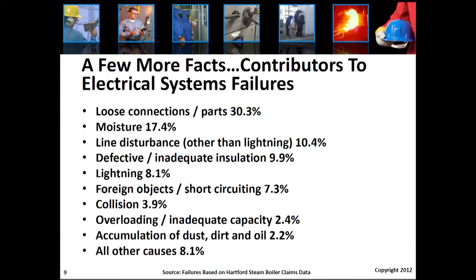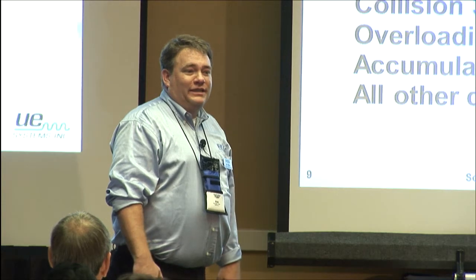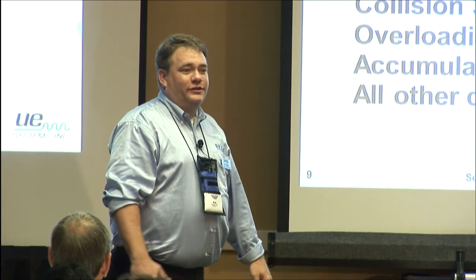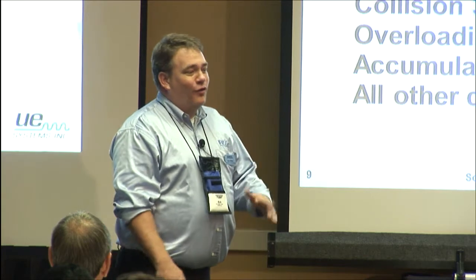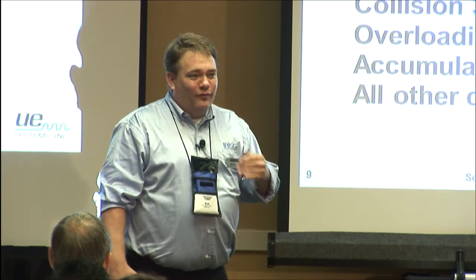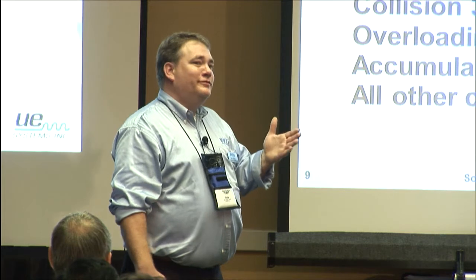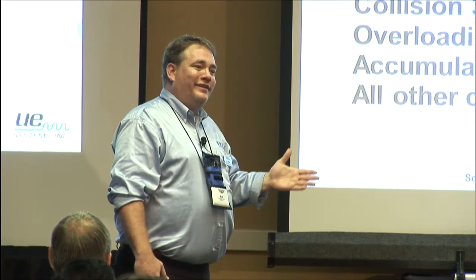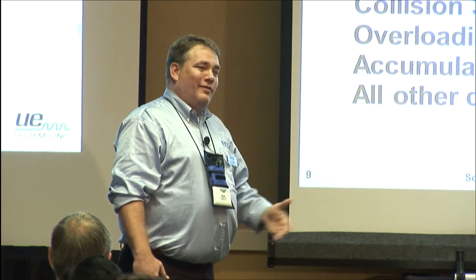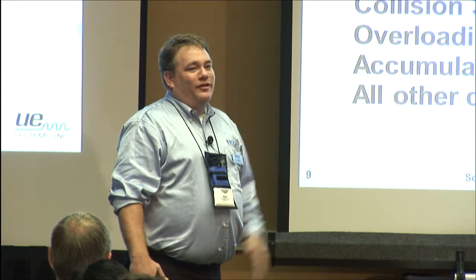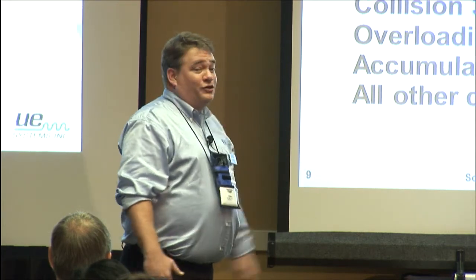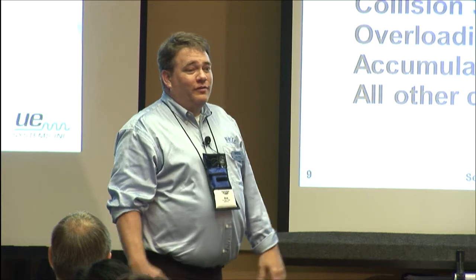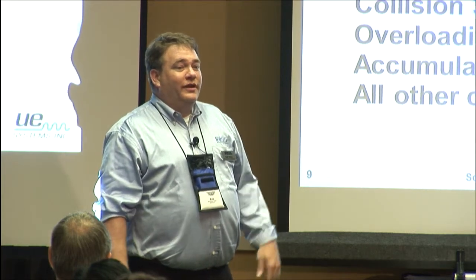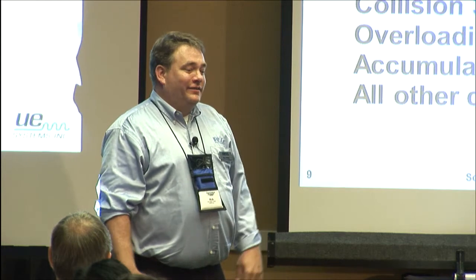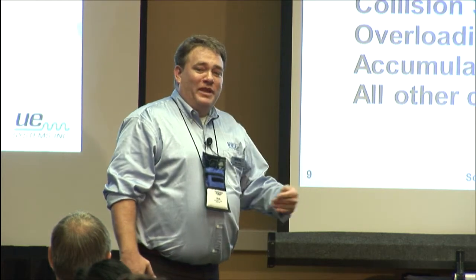Moisture accounts for another 17%, and that again goes to proper maintenance of the asset. Are you maintaining it the way the OEM says you should? OEMs tend to err on the side of caution, and you take that recommendation, and sometimes you follow it exactly during the warranty period, but as time goes on and things are stable, you back off a little. But honestly, moisture getting in there—there's really no excuse. If you're getting moisture inside your electrical distribution system, look at the root cause. Is it the cabinet's fault, or is it the lack of maintenance of that cabinet?